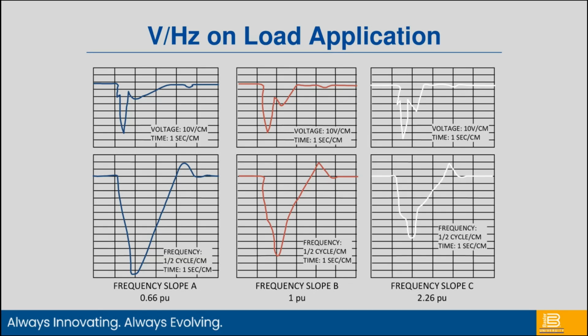Now, it could also be a trade-off. If we look at how quickly our voltage recovers, we have to tune that as well, because we may want to look at voltage recovery. So in this case, if you look at the top slopes, my voltage recovery on the 0.66 was pretty poor, actually, in both cases, voltage and frequency. But as I change that slope, I can see the recovery. My voltage may dip more, but because my frequency is recovering quicker, in the case of the higher, more aggressive slope, my voltage recovered quicker as well, basically because my frequency recovered quicker.